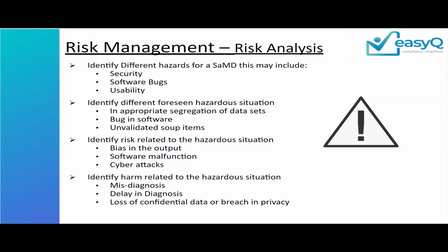That kind of hazardous situation is something that I rarely see people think about, but it's very important for you to ensure that if you're using a SOUP item, firstly, make sure that the SOUP item is not amongst the vulnerability list of SOUP items. Second, if you're using a SOUP item as part of your process, you need to ensure that the SOUP item is properly validated for its intended use for your product.